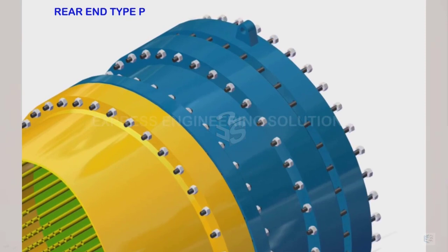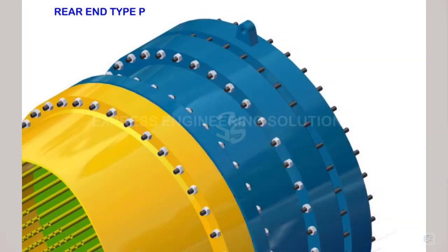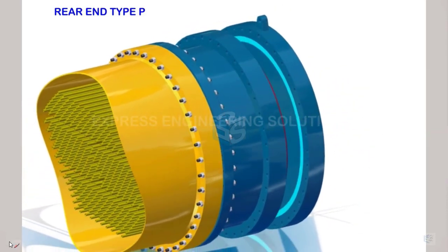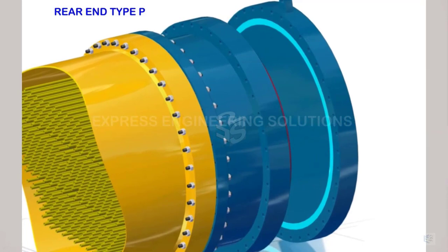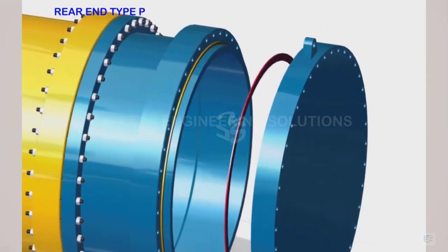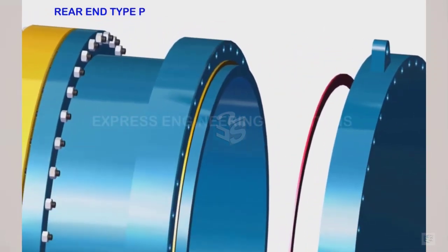In the 3D view: this represents the cover flange and this represents the loose flange. When the nuts are removed, the studs are also removed and the assembly is set free. The blind flange has a groove, and the gasket is placed inside this groove on the blind flange. The channel shell surface itself will compress the gasket against the groove on the cover flange.